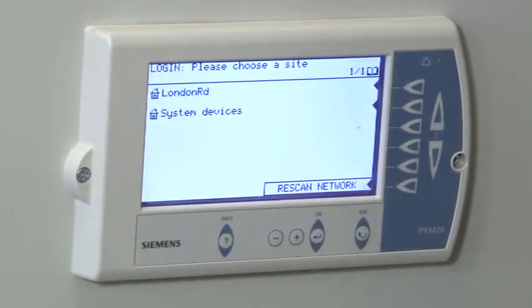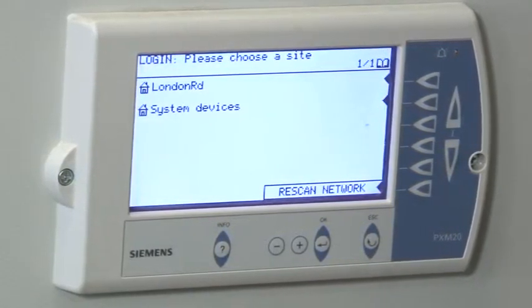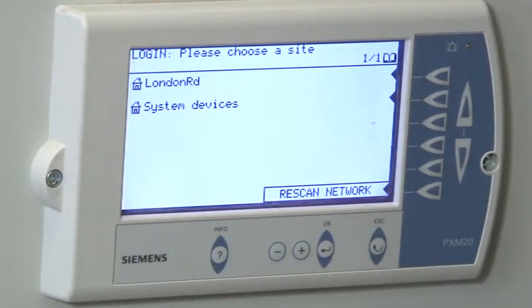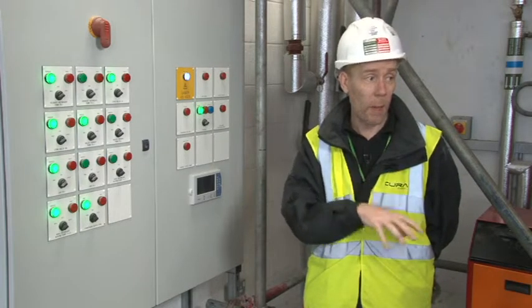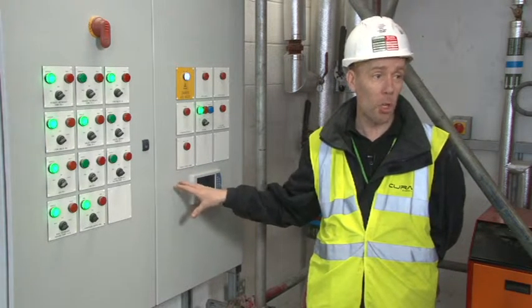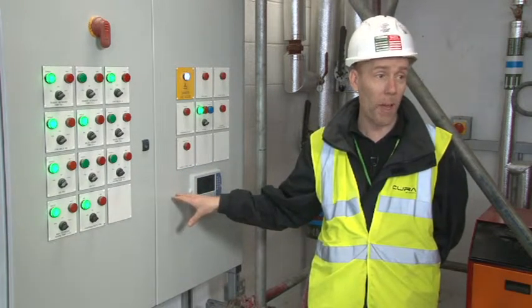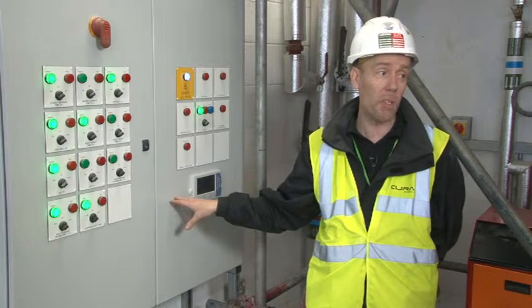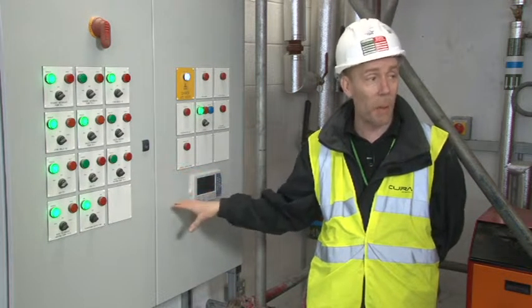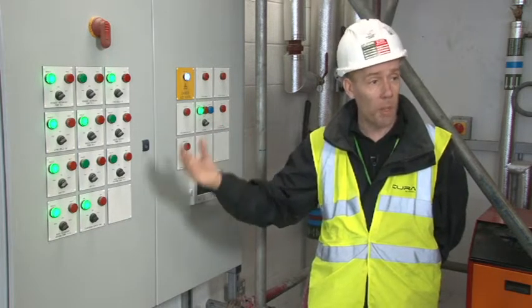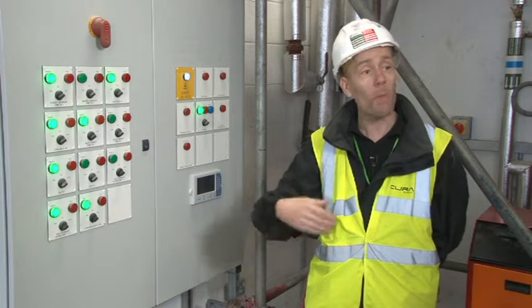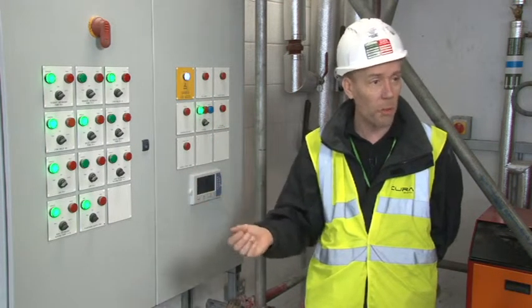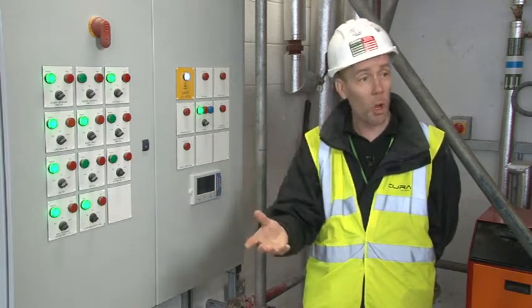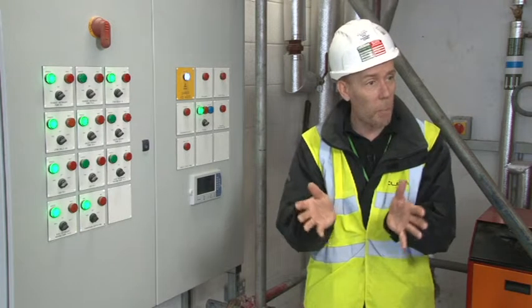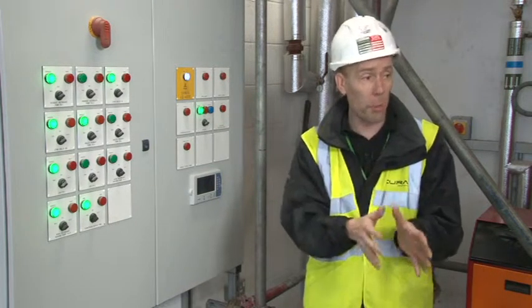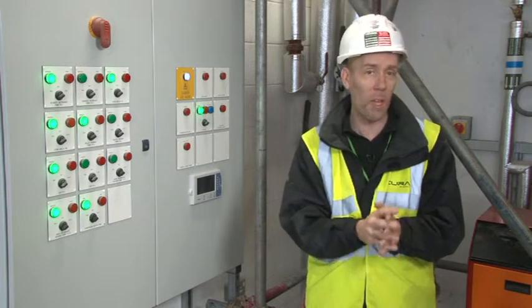To relay the faults back from this panel to the concierge, what we have is a head-end computer with installed software from Siemens. That software and that PC are tied to this system. Unfortunately, you can't change the PC, you can't change the software, and we don't recommend installing any other software on that PC. That PC operates a database to store when the alarm happens and when the alarm is reset and who reset the alarm. So if you have a maintenance company, A.N. Smith, doing your maintenance, they could come in, fix the alarm, sign in as A.N. Smith at 12 o'clock on the 12th of December, and there would be a record of that stored on that computer, which is why we don't recommend putting anything else or using it for any other purpose.